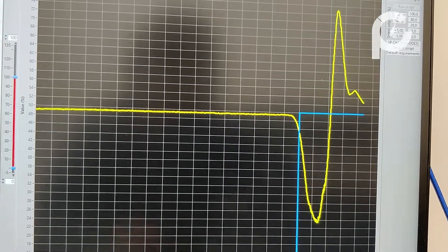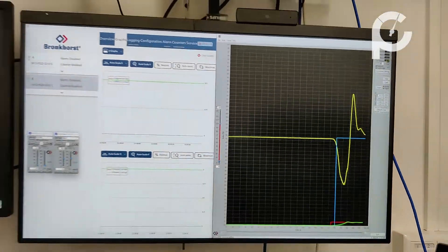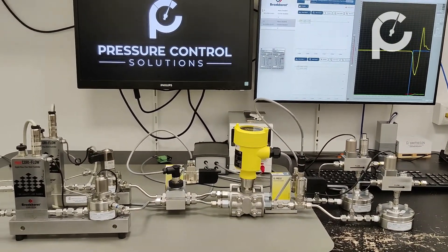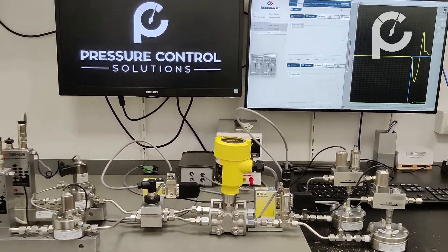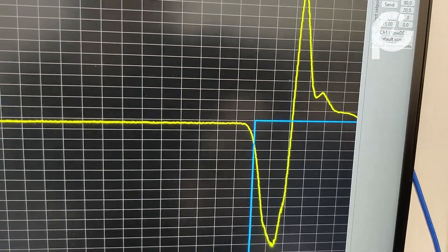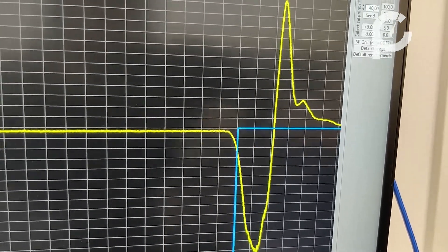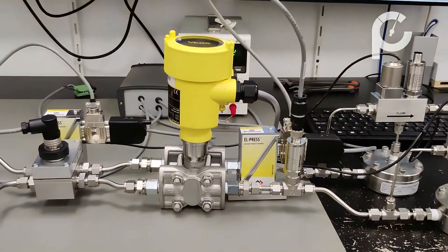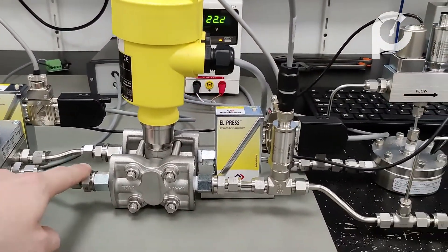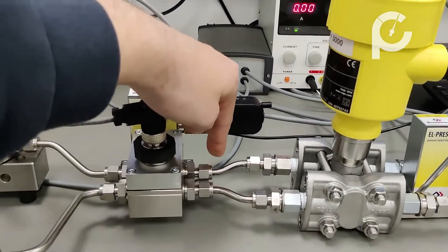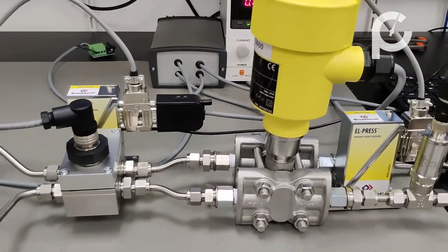Right now we are at a stable process pressure of 1.2 bar, and our delta P is controlling — we're nearly at stable conditions. Currently we have a stable delta P of roughly 10 milibars. This means we have a pressure here of 1.2 bars, and in this pipeline with a delta P of 10 milibars, you will have a pressure of 1.19 bar.